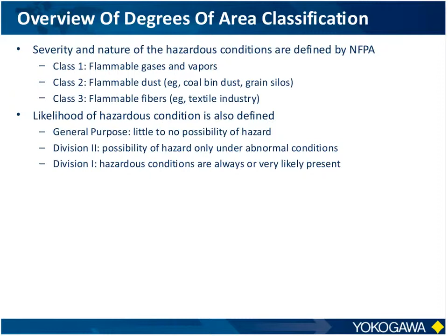This tells you, now that you know the possibility and the type, how easy it is for ignition to occur. For example, groups C and D are your typical hydrocarbons, but things like hydrogen and acetylene are much easier to ignite, so they might be group B or group A, which puts more severe restrictions on the type of electrical equipment that can be used.